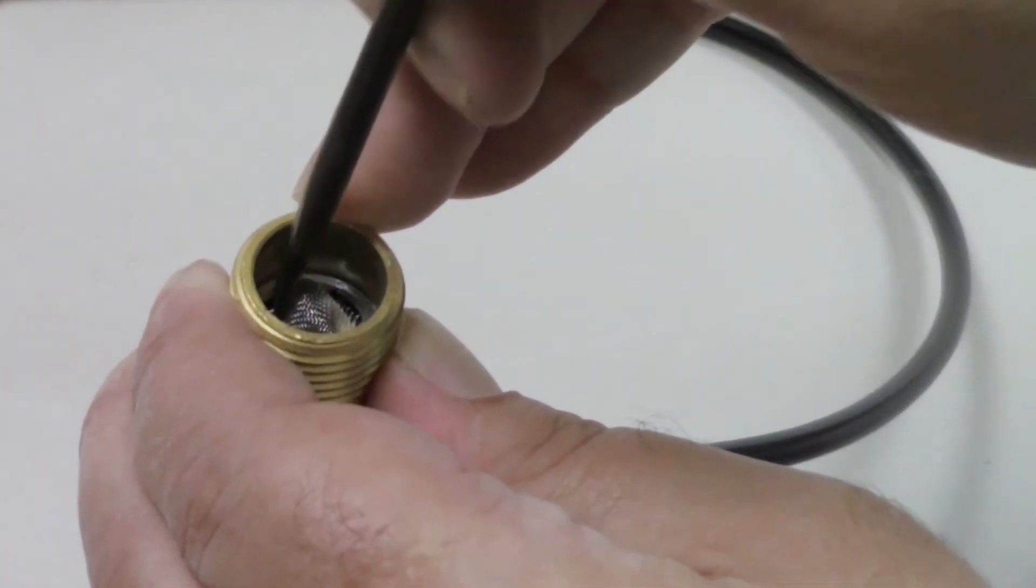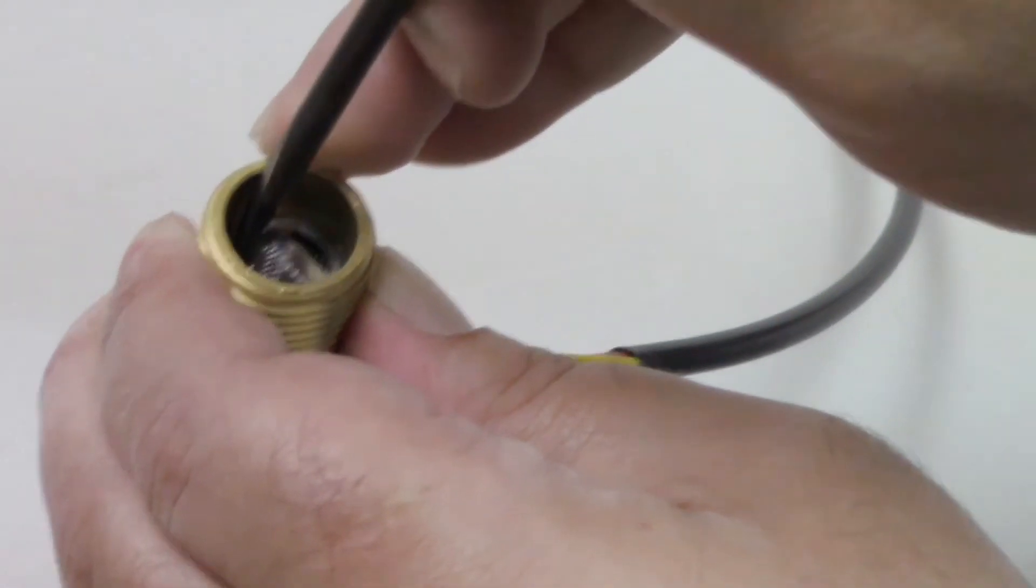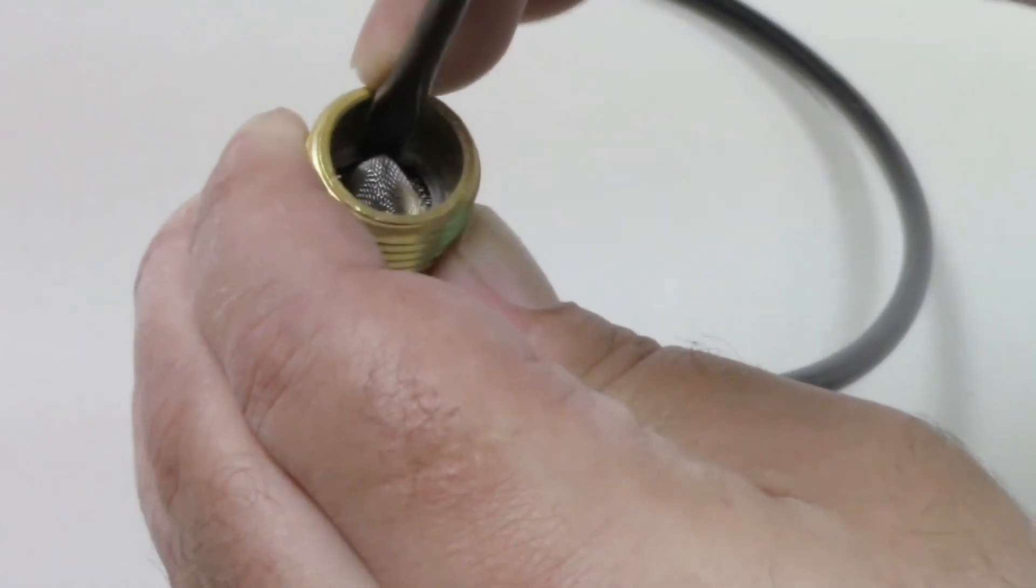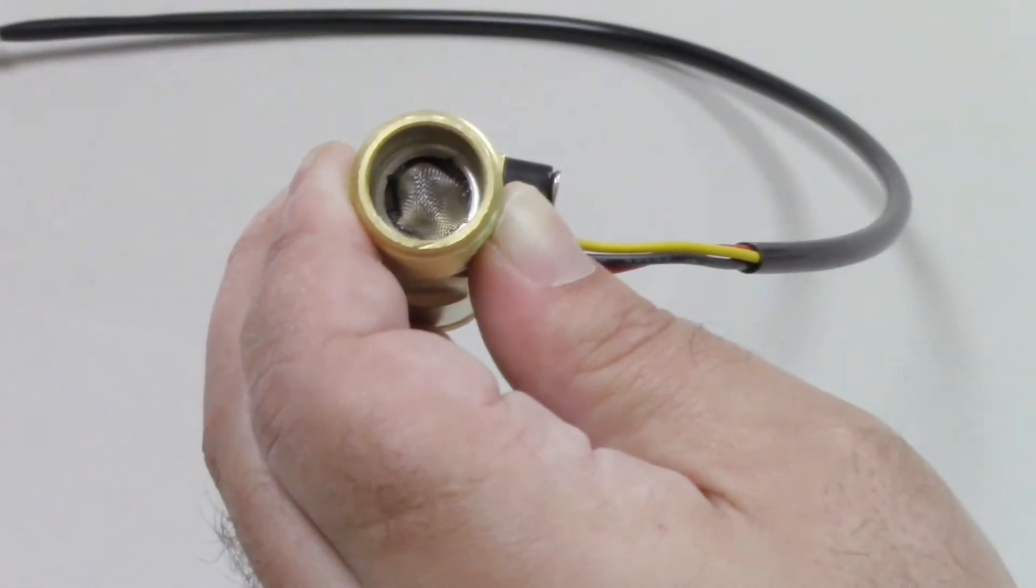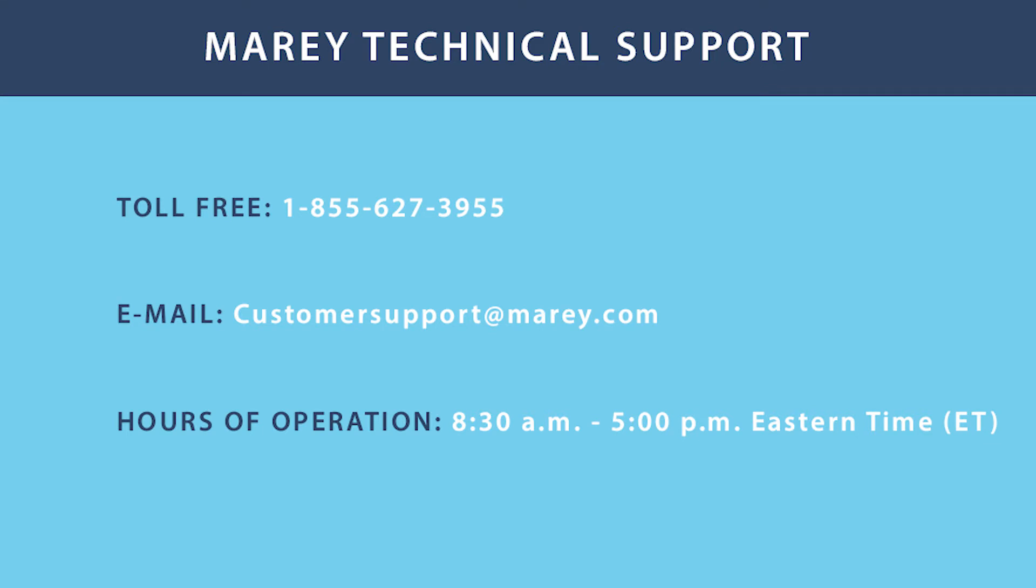If the flow switch spins freely and the problem continues to persist, then your unit's flow sensor may have malfunctioned and will need to be replaced. Please contact Marey Technical Support for further assistance.